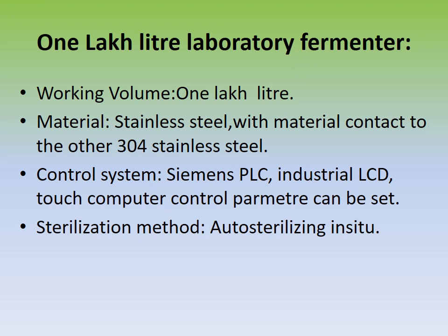Normally, we can say that it has internal coils, which provide a mechanism for vessel sterilization and temperature control during the fermentation. For the control system, we should provide Siemens PLC industrial LCD touch computer, and control parameters can be set. In the sterilization method, an auto sterilizing condition will be provided. So the 1 lakh liter fermenter also has foam control, temperature control, and pH control.